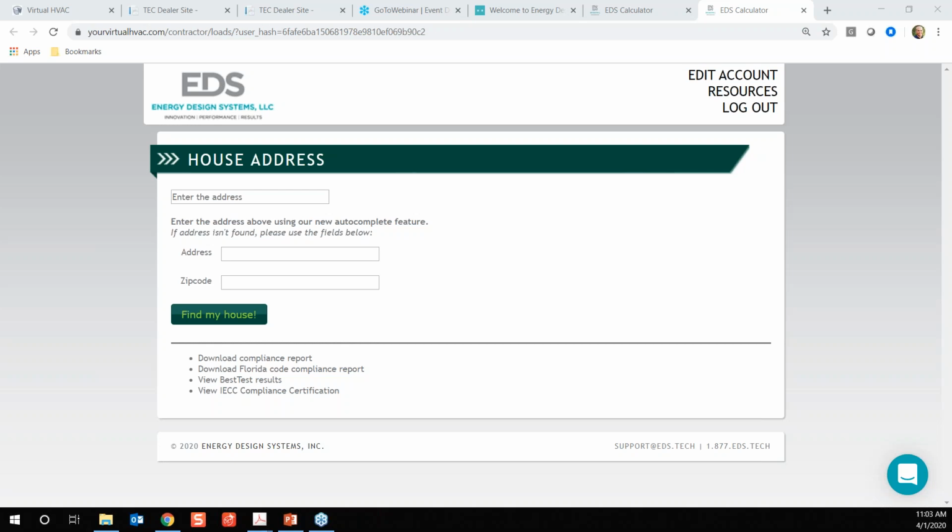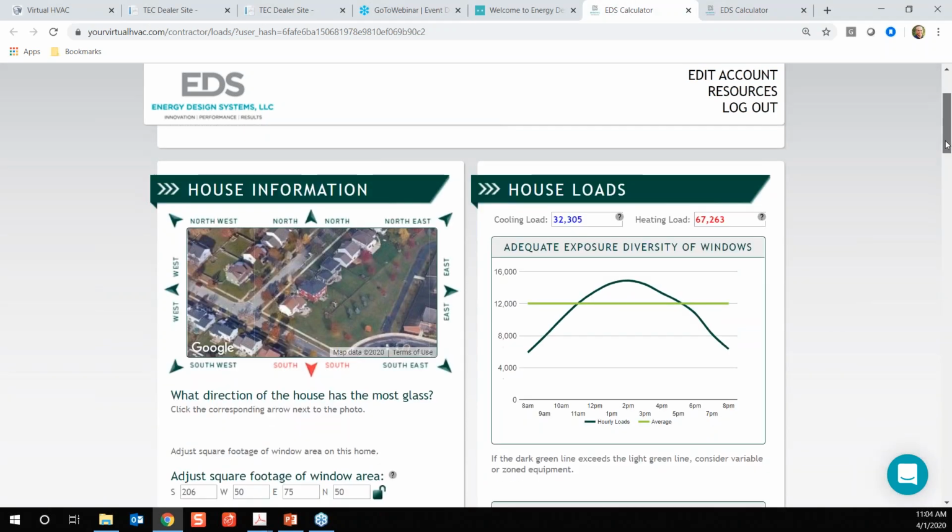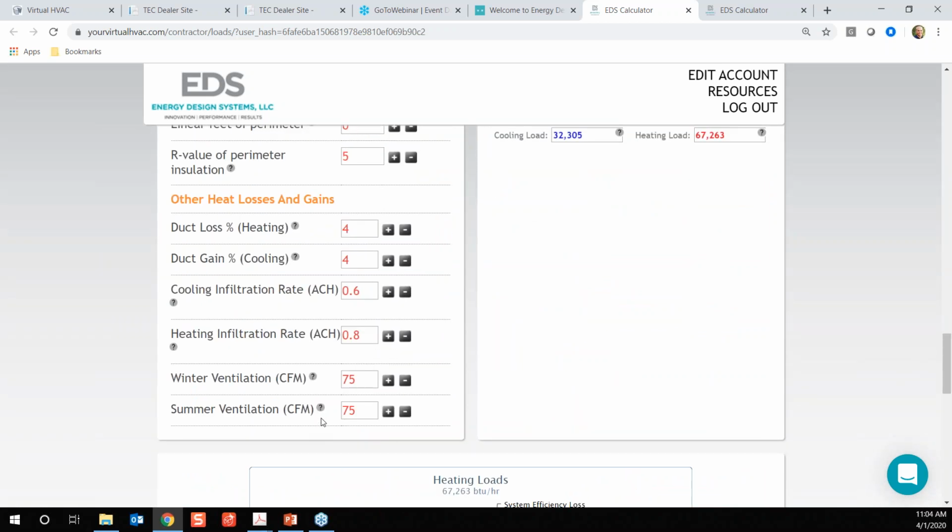Okay, my question is, what if we increase the percentage of fresh air since there are many options like air-to-air heat recovery options such as enthalpy wheels and sensible and latent energy recovery? So this tool, when we're looking at that ventilation infiltration air, so let's say I made the house really tight and then I put an ERV in. So I would drop these leakage rates down. And then let's say my ERV was, I'll make my life easy, let's say it's 100 CFM. Well, this tool is going to assume it's 100 CFM of raw air. So that means, in my case, 3 degrees in the winter and 89 degrees in the summer.